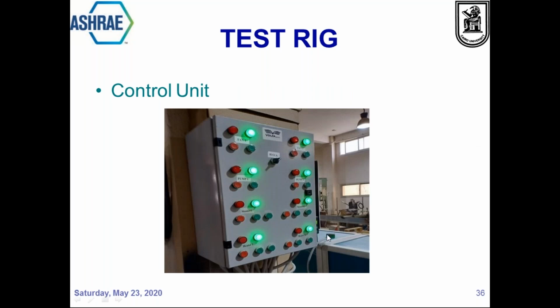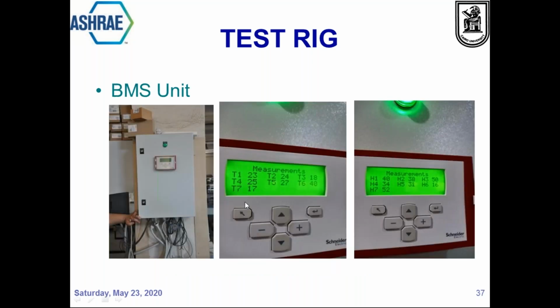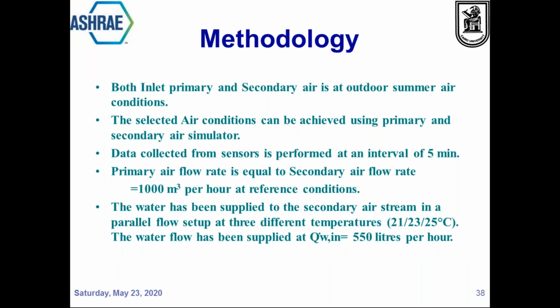Naturally, we have a control module, PLC, and the results come out to a laptop or computer where results are recorded. In order to do this process, we measure temperatures with thermocouples, flow rates by nozzle, and we have also wind anemometers to measure the air velocity, hygrometer to measure the humidity ratio, power and current to be measured electrically.